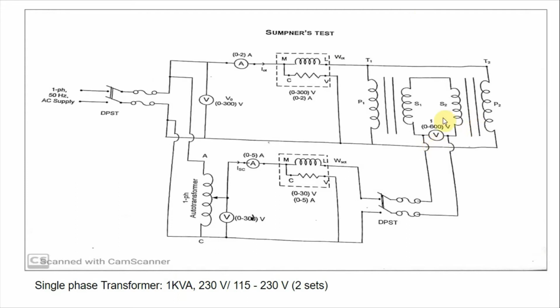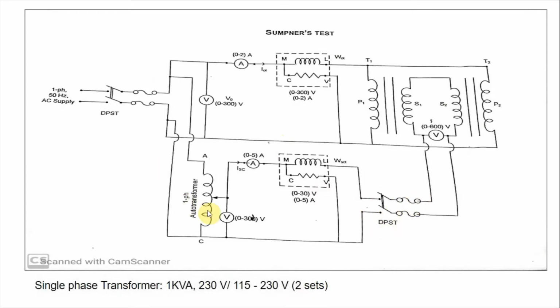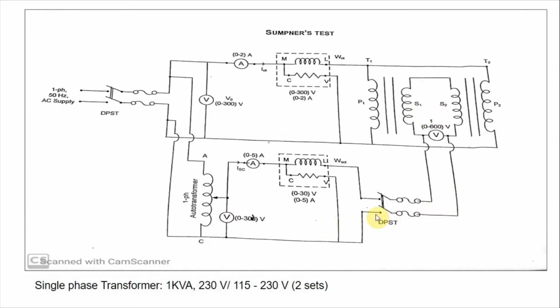After we have ensured the secondary opposition, we will take the meter readings. Now that will be the no load reading. After that, we will close this DPST switch. Now we will inject a small voltage into the secondary with the help of a single phase auto transformer, such that the rated current flows through the secondary of the transformer. Thus, this way we can simulate the short circuit test. These 3 meters give us the short circuit reading.